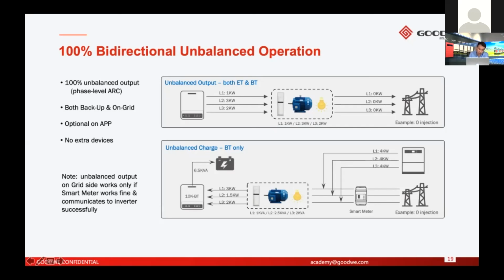So if the inverter cannot support unbalanced charge, it means the charge power to the AC coupled inverters must be the same on all three phases. This is the same logic as the unbalanced outputs actually. If the inverter cannot support unbalanced charge, there is a lot of waste of solar power. But for BT, our three-phase AC coupled inverters, we have realized this function. They can do unbalanced charge for the batteries connected on the AC coupled side.